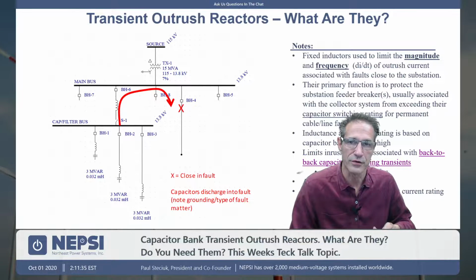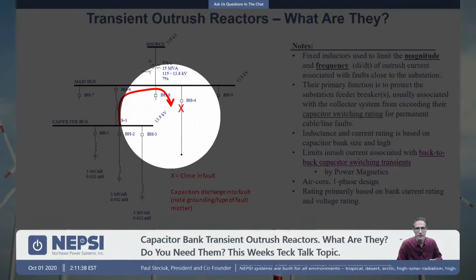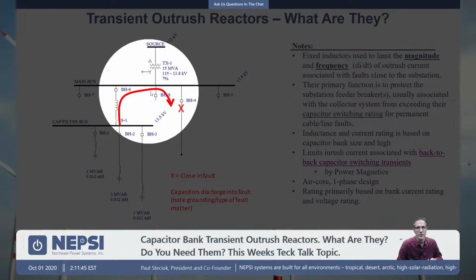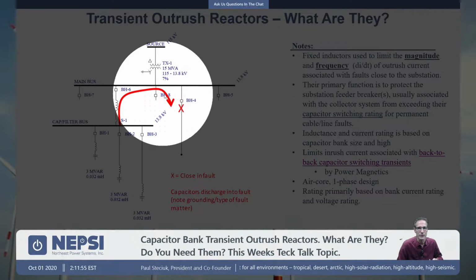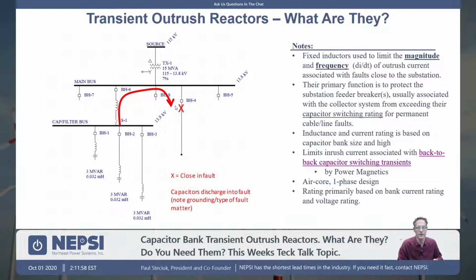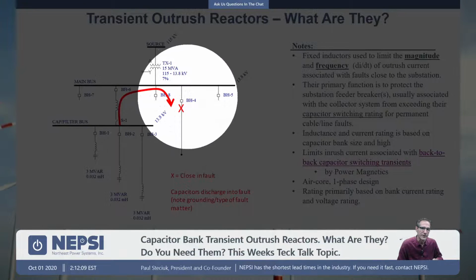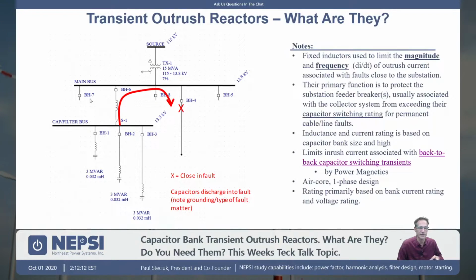So just to repeat, to make sure it's clear, we have a situation where we have a permanent fault on BH4, and the capacitor bank here is running. So if the capacitor bank is running, we have a fault here at this location or somewhere along this line, and they energize this breaker into that fault. And the discharge current here will discharge through that breaker at that moment in time, and you're dealing with the transient making current of the breaker at that time. And that is the issue. So very often BH4, BH5, BH7, they are just general purpose breakers. C0 rated breakers are not rated for restrike, and they can't handle that transient outrush current, and that can result in damage to the breaker.